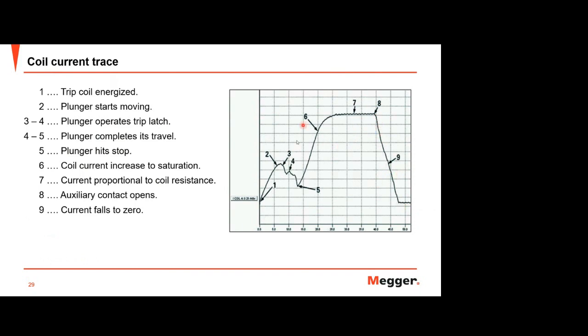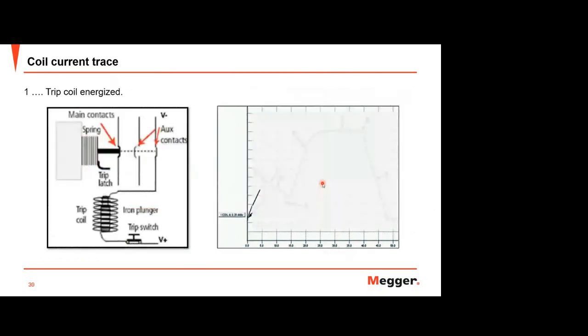So meaning this, from 5 to 9, is mostly affected by the mechanism of the circuit breaker, and from 1 to 5 it is more or less affected by the latching and your coil, the coil that triggers the mechanical part of the trigger. So maybe I will try to explain more clearly with this picture.